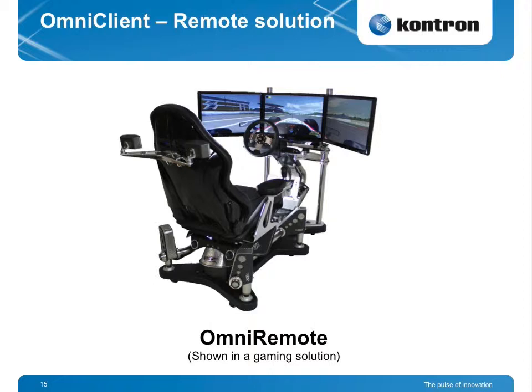The true representation of what the Omni remote would be used for would be where the display can be next to the machine, but the processor is protected away, maybe underneath the machine, under an access panel. So it's not in the extreme environment that the display would be in. Because the rear section is only an IP20, which is ingress protection, there may be high humidity, high smoke, dust, so you want to protect that one. But the front panel is actually IP65, which means you can spray with water, etc.